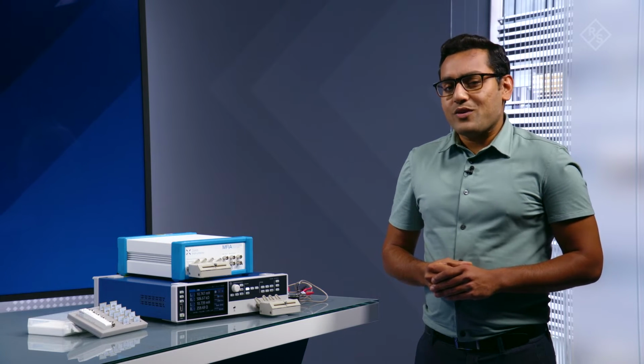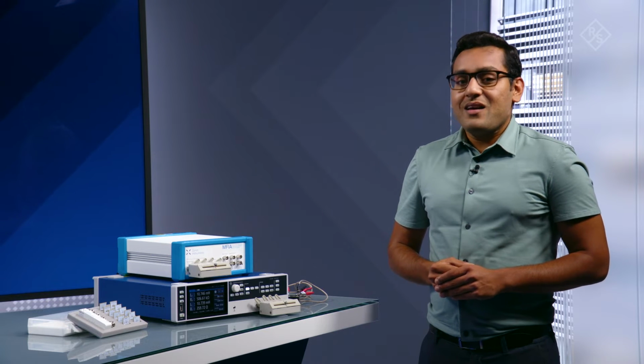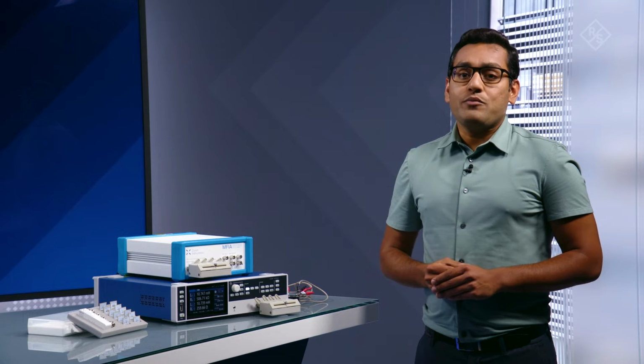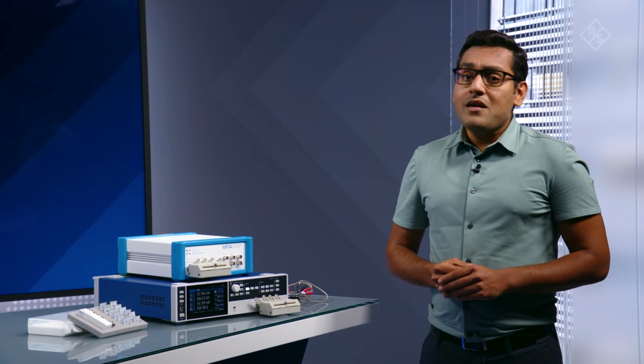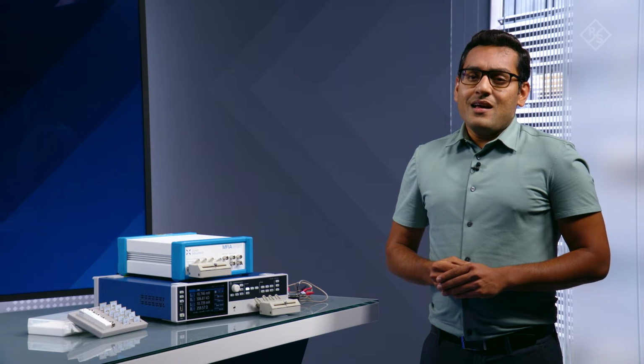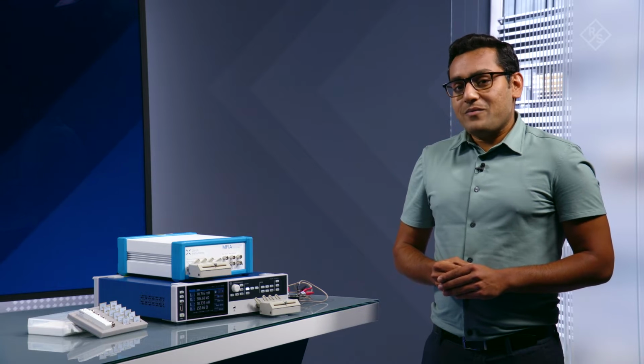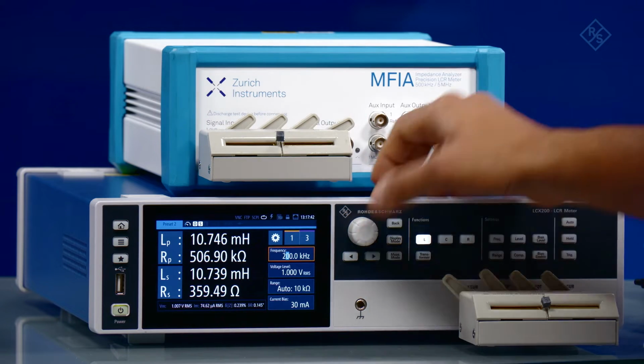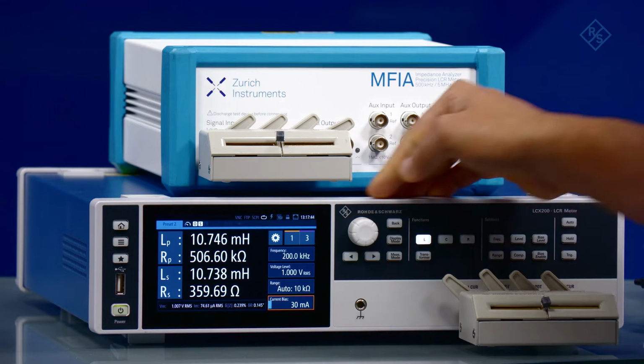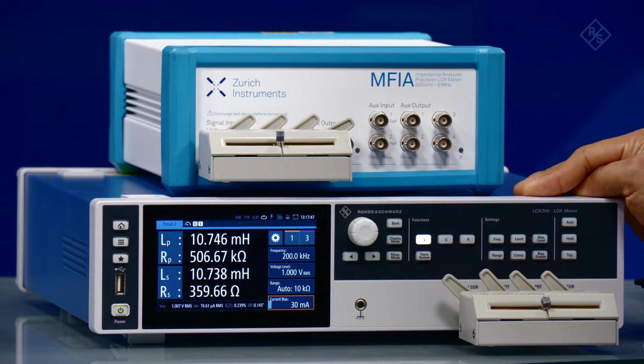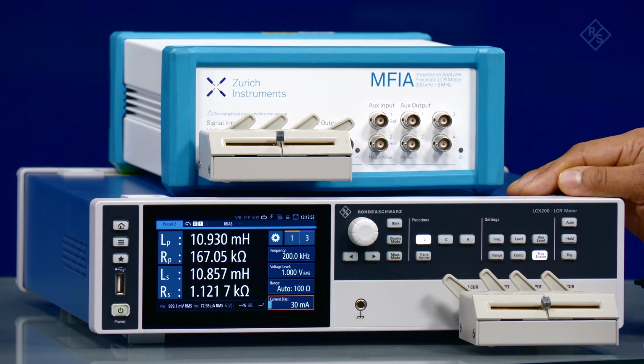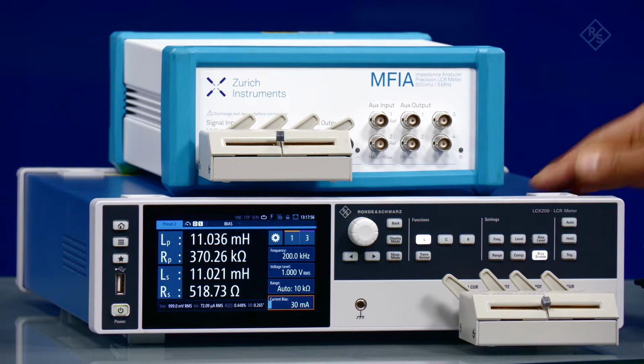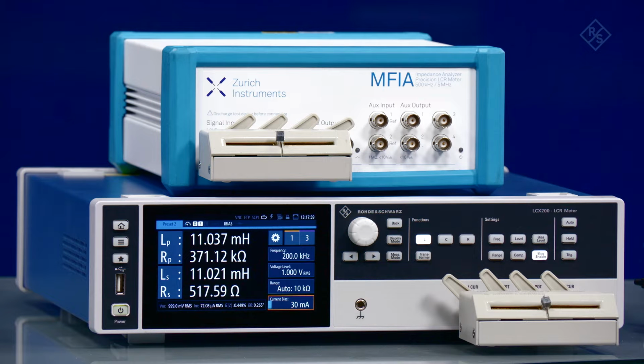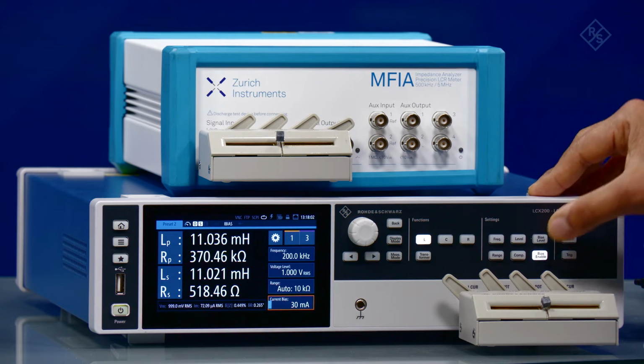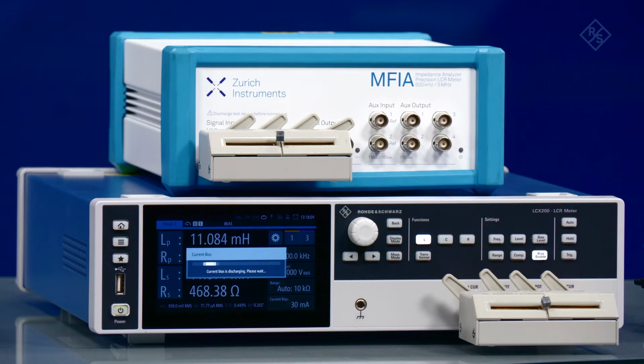Now, do you need a current bias for the inductor? The LCX200 has an optional DC internal bias current source up to 200 mA, which can be enabled with option LCX-K108. Let's add some DC bias current to our inductor now. Let's enable the current bias by pressing the bias enable key, which lights up to indicate that the bias is active. Let me deactivate the bias now and show you some additional functionalities of our LCX200.